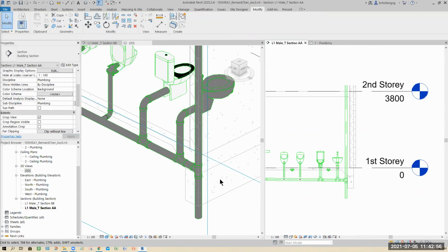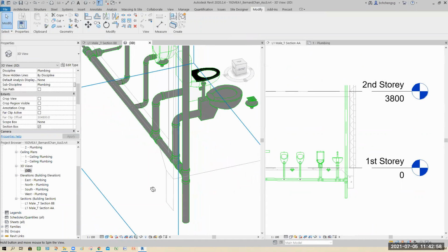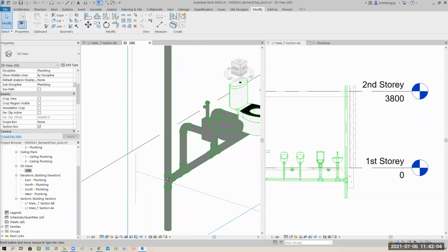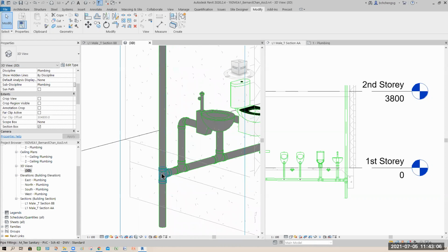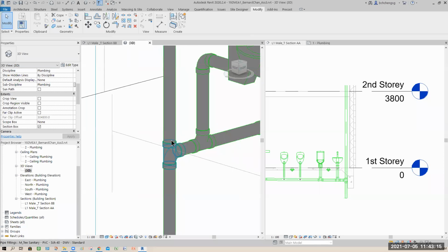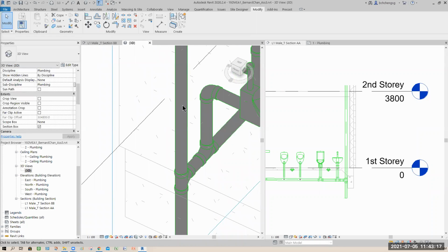But right here should have something for us to clear the choking, which is, if this is a big enough pipe in Singapore, in our design there's an opening to clear the choking. But because this is a small pipe, they have to add some fitting here to act as a choking clearance.